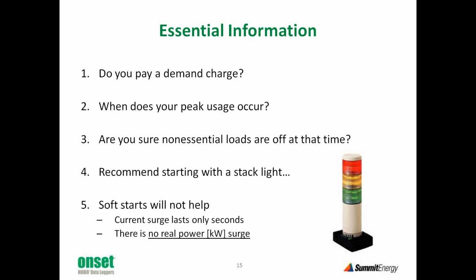Now, number 5 is a common mistake that I see. Soft starting motors will not help. Some of you may think that, say we have a 500 horsepower motor, maybe it's a chiller or an air compressor or it's a blower or something associated with production. And it is true that if you start a large induction motor, particularly across the line, there's an enormous inrush current. That inrush current should not be confused with real power. There is not a surge in real power, and soft starting that motor will not help with demand management in any way.